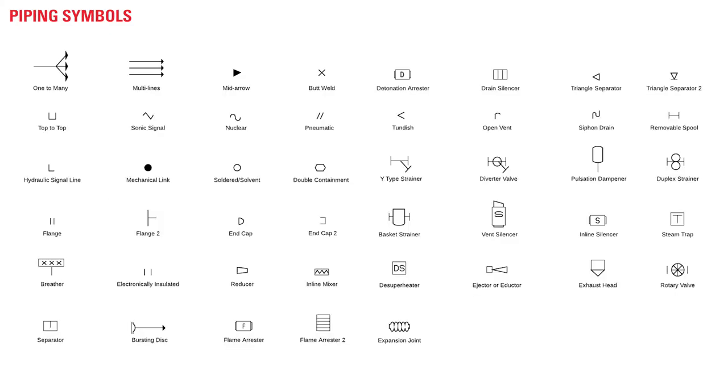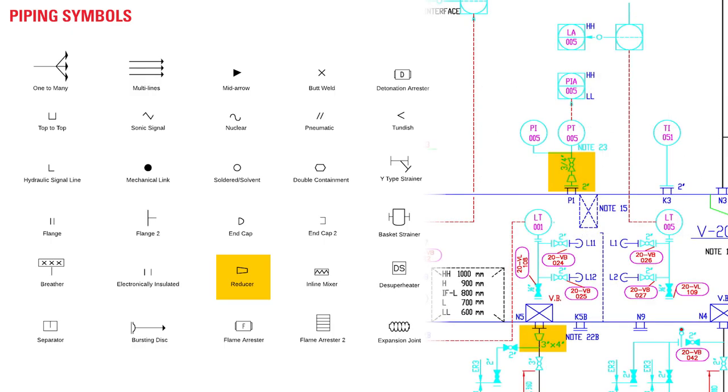Piping symbols have various important uses you want to be familiar with. One important symbol to note here would be the reducers. This will help you identify when the piping changes sizes. You'll see these sometimes immediately upstream or downstream of a control device. This information is helpful for understanding flow capacity and sizing.